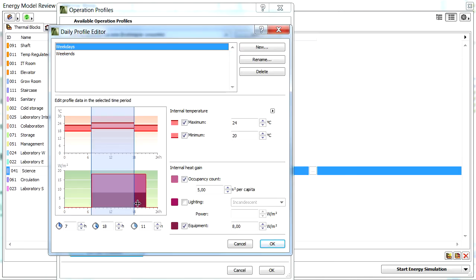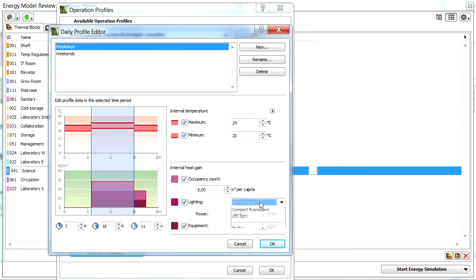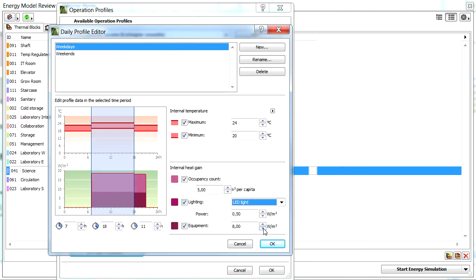Let's also adjust the internal heat gain values. We will leave the occupancy count unchanged, 5 square meters per capita. We will specify LED light for lighting, and 0.5 watts per square meter of power. We will specify 8 watts per square meter internal heat gain value for the equipment.